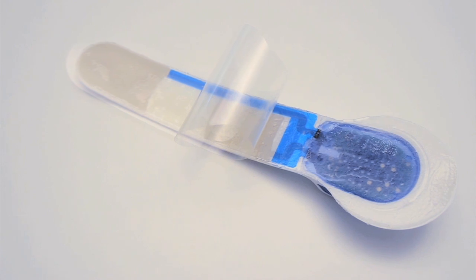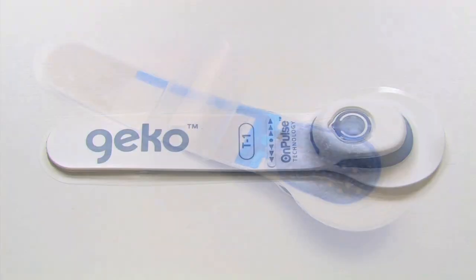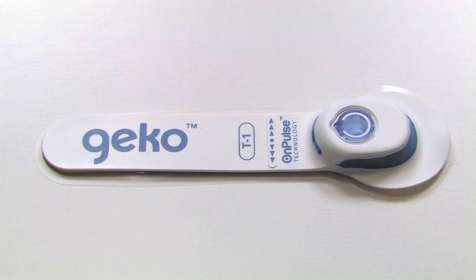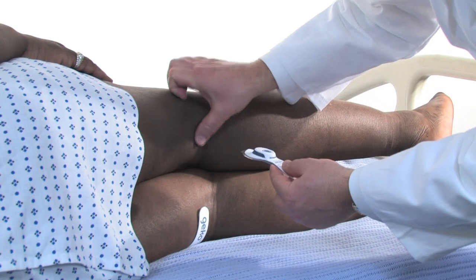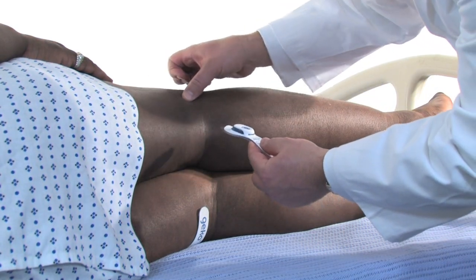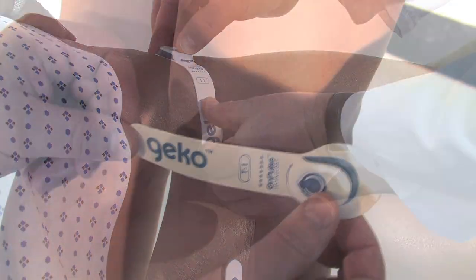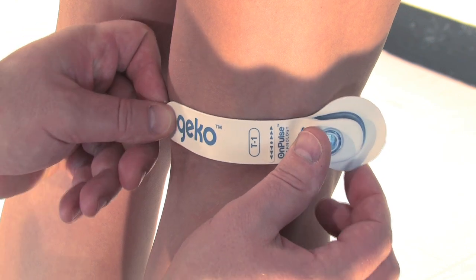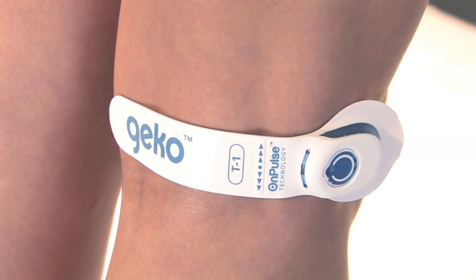A disposable, easy-peel backing film protects the hydrogel before use. The geko device is a daily disposable, one-size-fits-all device. It will even fit adults with a very large leg circumference, up to 24 inches. It can be fitted with the patient lying down or standing, and its small geometry assists infection control and may reduce the risk of pressure sores.